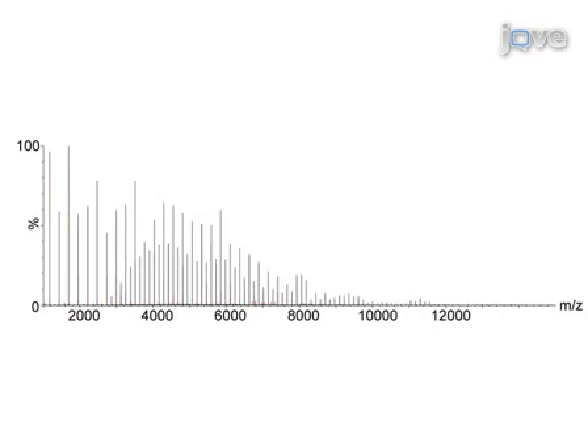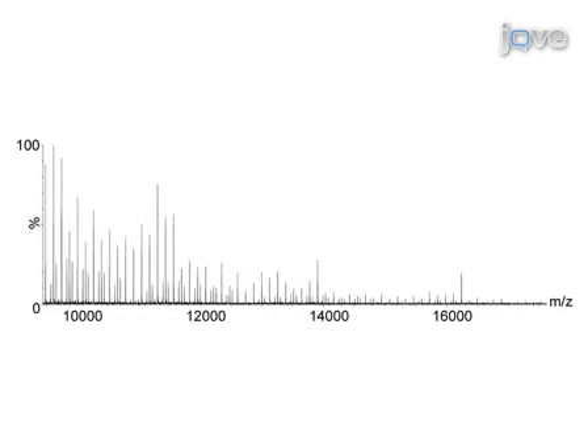Increasing the pressure at the initial vacuum stage is essential for detecting the high mass clusters. The effect of pressure on the high mass peaks is demonstrated here with pressure readbacks of 1.2 and 5.3 millibar. The mass spectrum for the higher pressure is shown expanded here.